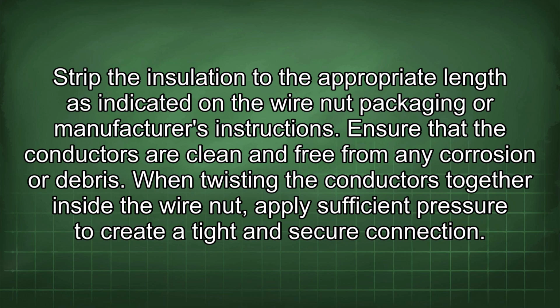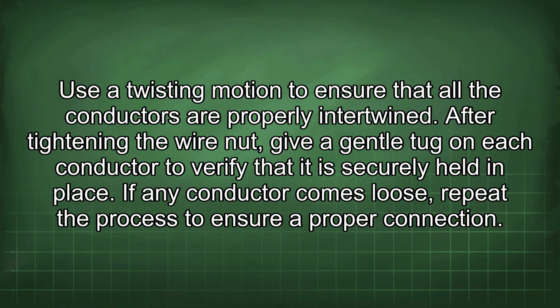When twisting the conductors together inside the wire nut, apply sufficient pressure to create a tight and secure connection. Use a twisting motion to ensure that all the conductors are properly intertwined. After tightening the wire nut, give a gentle tug on each conductor to verify that it is securely held in place. If any conductor comes loose, repeat the process to ensure a proper connection.